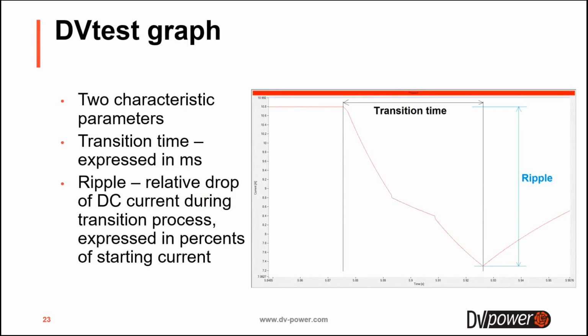So on this DVtest graph, besides those characteristic parts of the graph, we have two parameters: transition time and ripple. The transition time is the time which is necessary for the OLTC to move from one tap to another. It is the time from the moment when the current starts to drop until the moment when the current starts to rise again to the new value. That is represented here with vertical black lines. This transition time is expressed in milliseconds.